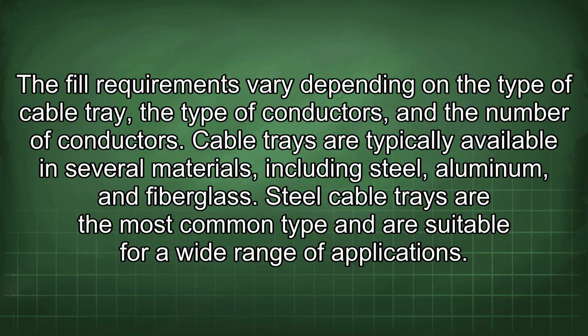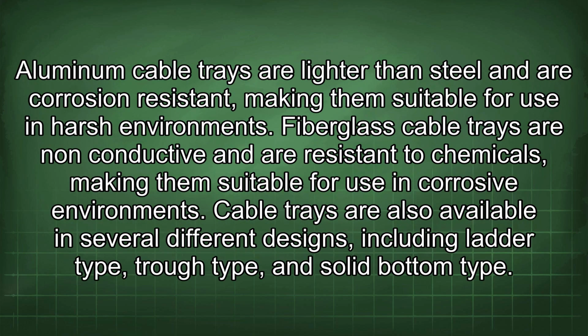Steel cable trays are the most common type and are suitable for a wide range of applications. Aluminum cable trays are lighter than steel and are corrosion resistant, making them suitable for use in harsh environments. Fiberglass cable trays are non-conductive and are resistant to chemicals, making them suitable for use in corrosive environments.